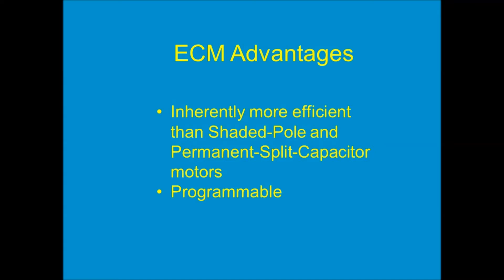Next, it's programmable — a really interesting feature. All the fans we provide from the Loren Cook Company can either be balanced in the field by turning a screw right on the motor, if you just need a single CFM, a straight steady flow. However, you can also bring a low voltage control signal to the motor and ramp the motor up and down as needed.